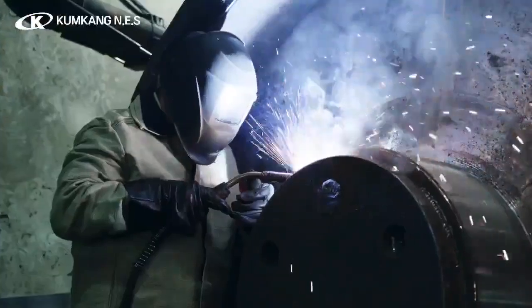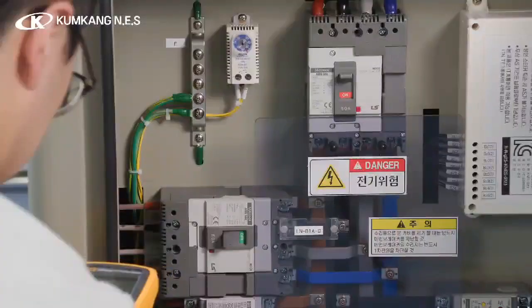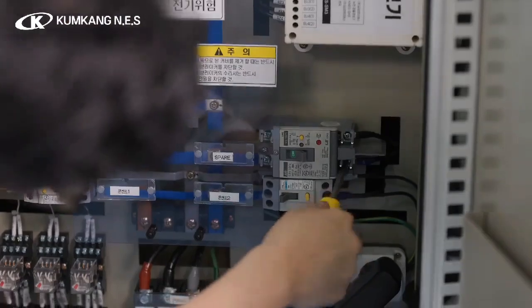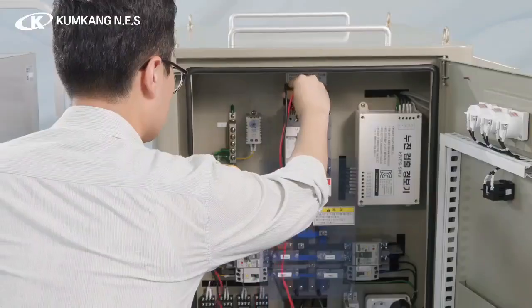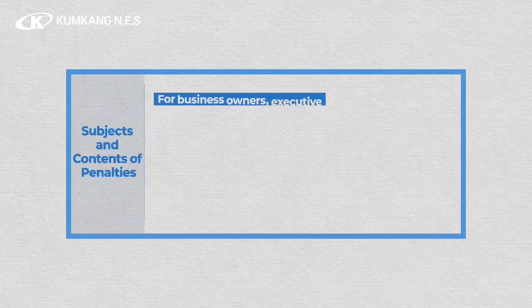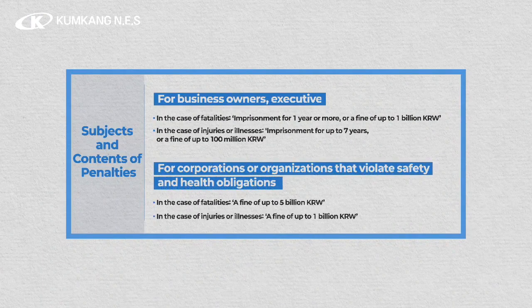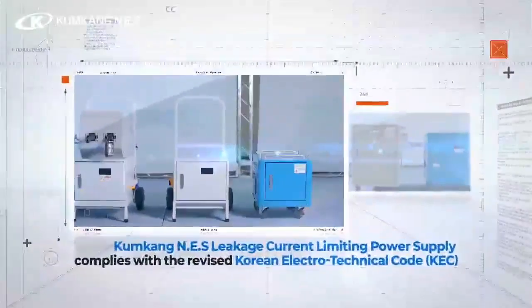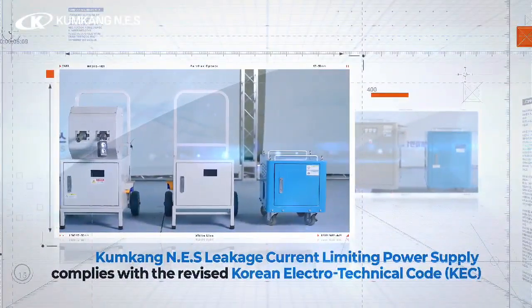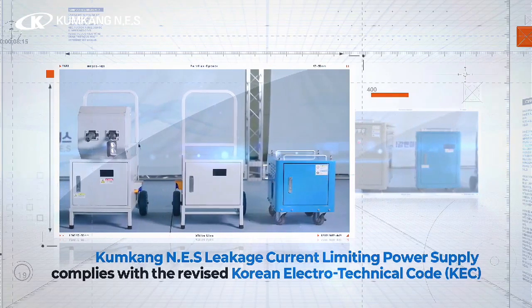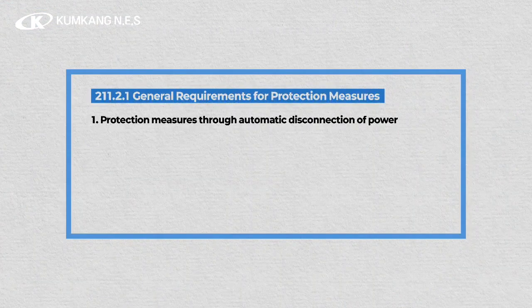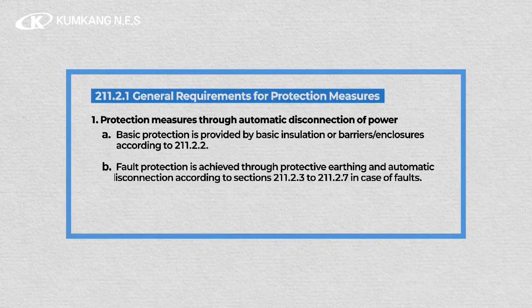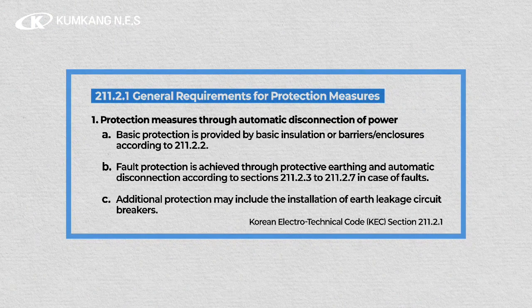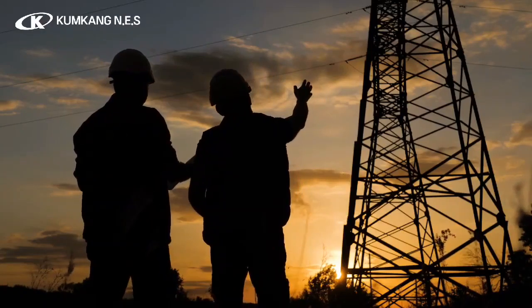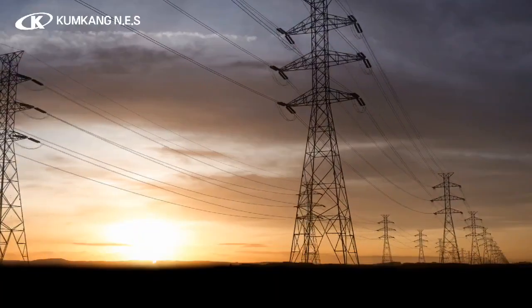73% of electrical shock accidents occur during electrical work or maintenance work by managers. The leakage current limiting power supply secures electrical shock safety through IT system conversion, alleviating the management burden at sites where it is required to comply with the Serious Accidents Punishment Act. Kumkang NES leakage current limiting power supply complies with the revised Korean Electrotechnical Code, KEC. The revised KEC redefines earth leakage circuit breaker, previously used for primary protection against electrical faults, as an additional protective device and requires fundamental protective measures for safety.